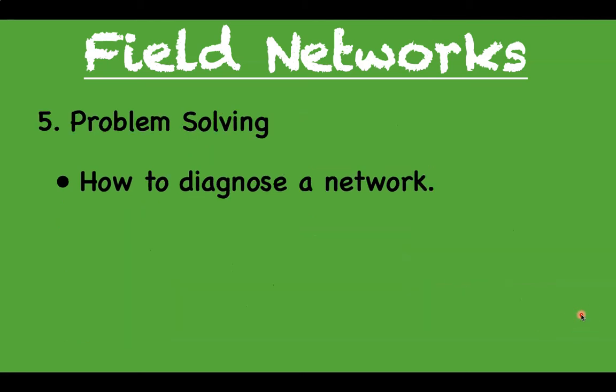Then the next point is problem solving. When it comes to this, you should know how to diagnose a field network. Of course, you can't know how to diagnose every type of field network. It is just that there is a theme here as well. Typically, a field network will be Ethernet TCP based or serial 3-wire, 2-wire, or anything that is not Ethernet.